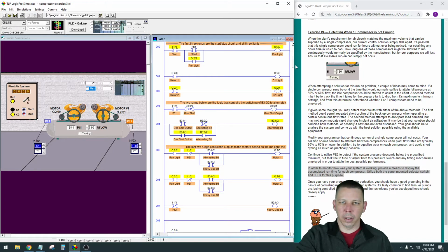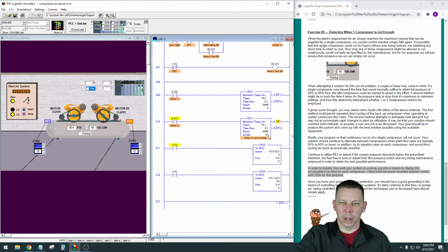Let's go down and look at this timer. Okay. Motor 2 is running. Motor 2 contact here is true, which is enabling this RTO. That's why it's counting up. And you see the accumulated down here in this display. If I go to B, there you go. So there's my display. And it's displaying the accumulated value of the timer that runs when motor 2 is running.